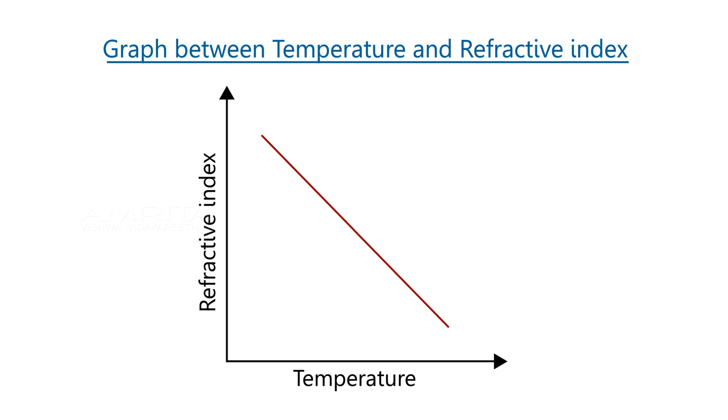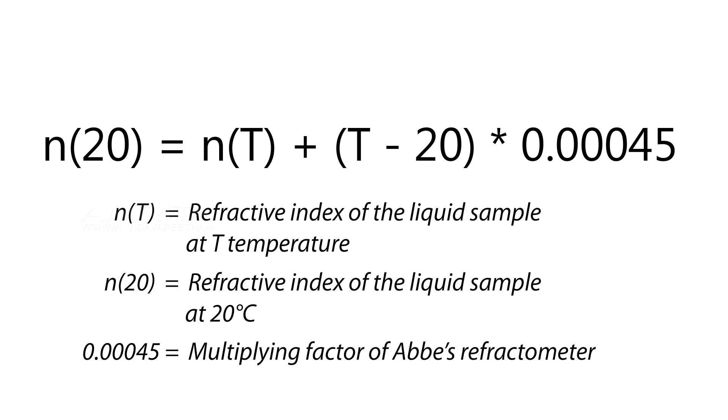The variation can be defined by equation: n₂₀ = nₜ + (t - 20) × 0.00045, where nₜ is the refractive index of the liquid sample at t temperature, n₂₀ is the refractive index of liquid sample at 20°C, and 0.00045 is the multiplying factor of an Abbe refractometer.